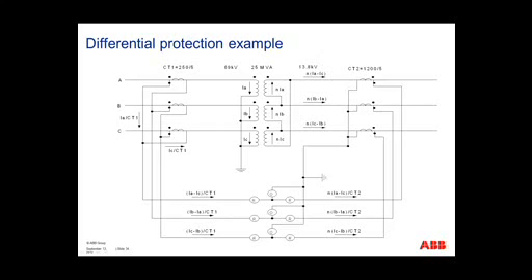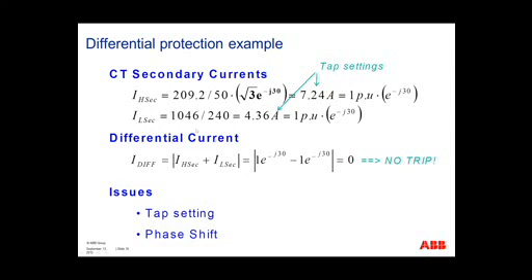So to do this correctly, and once again, this is before microprocessor-based relays, if we're using solid-state relays, we would have to connect our CTs on our high side in delta. When we do this, looking at A phase, we now have A minus C current coming into the relay. We have a Y-connected CT on the low side, which reads A minus C, and we can see our currents will be balanced. We do our calculations, look at our CT secondary currents divided by our CT ratios, account for our square root of 3 on the high side, and add up our differential current. Because we have accounted for that 30 degree phase shift on the high side, our currents are balanced. We will have no trip.